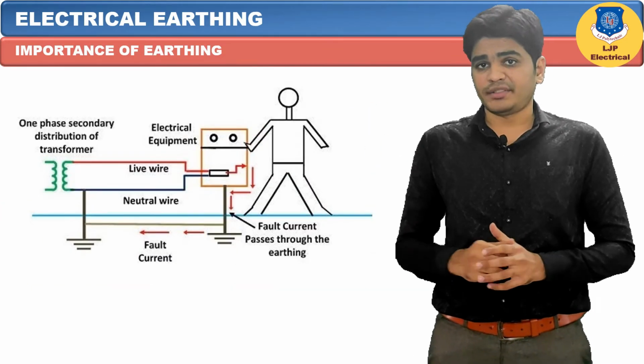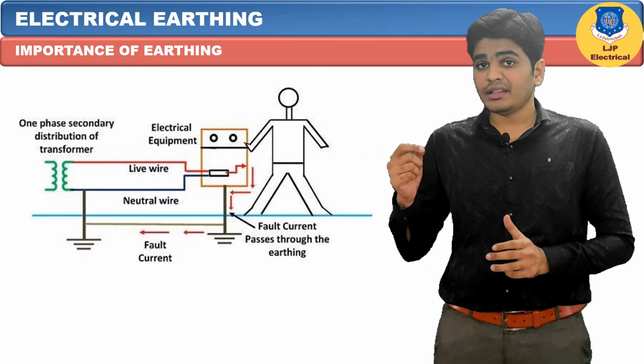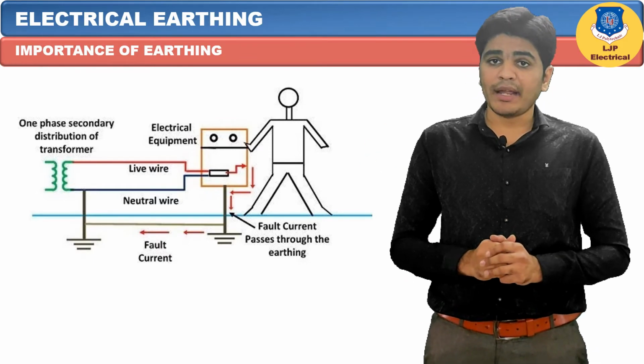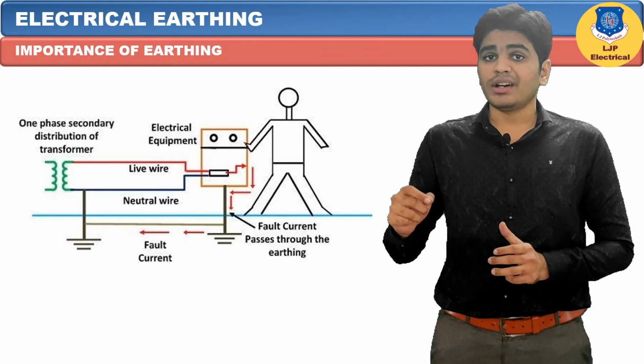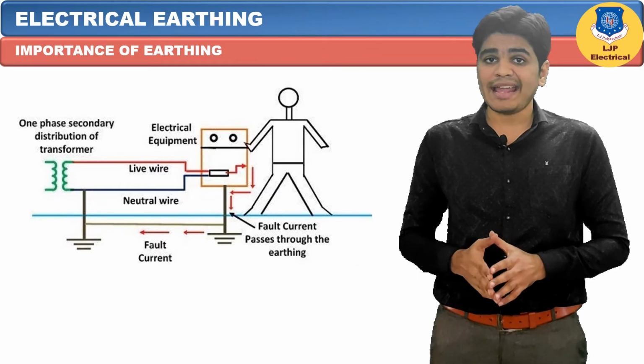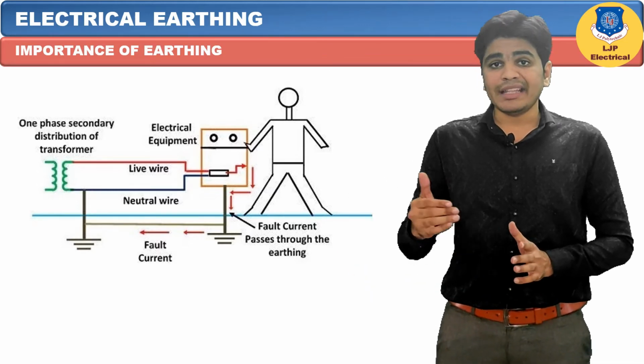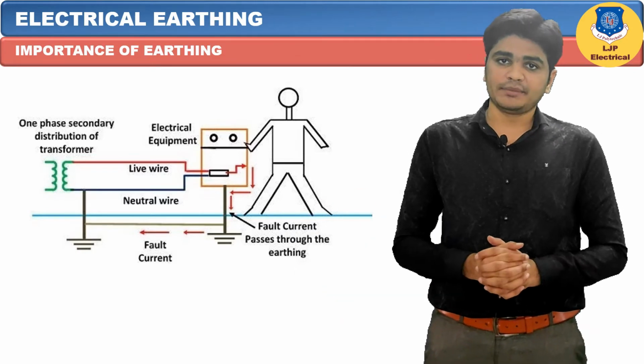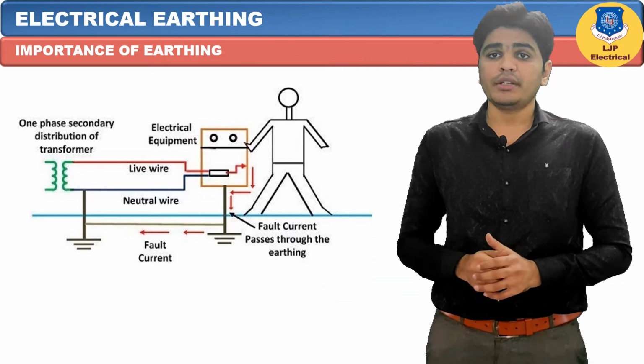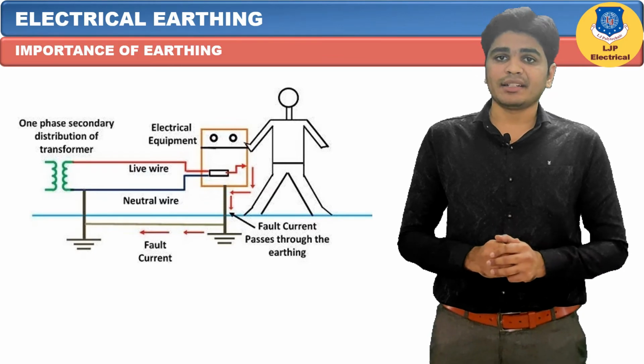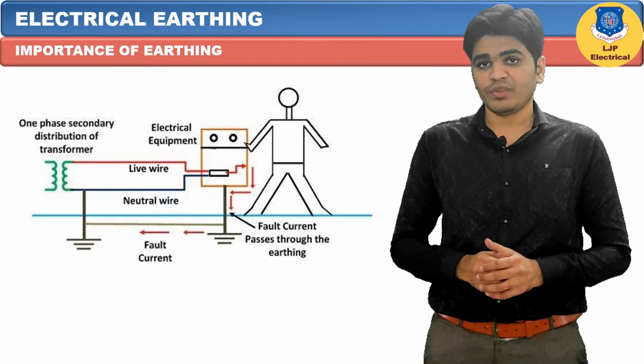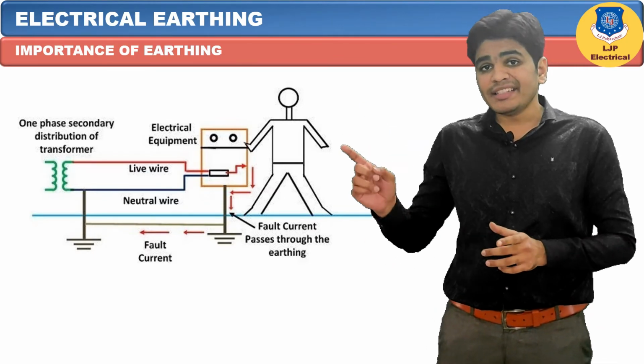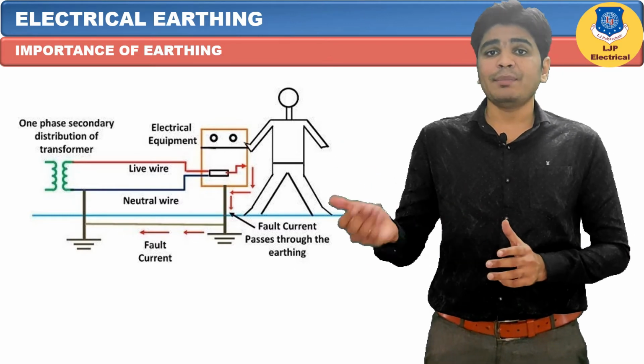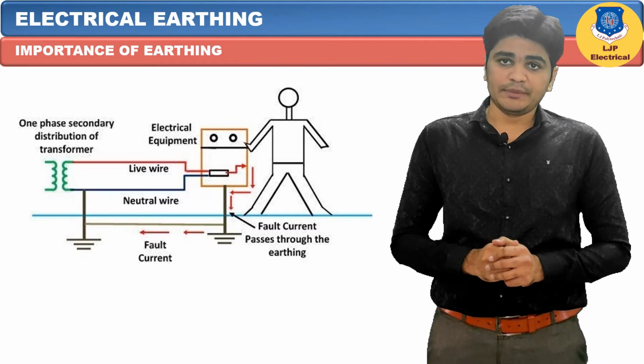When a fault occurs, you can see here the fault current from the equipment flows through the earthing system to the earth and thereby protects the equipment from the fault current. At the time of the fault, the earth mat conductors rise to a voltage which is equal to the resistance of the earth mat multiplied by the ground fault current.